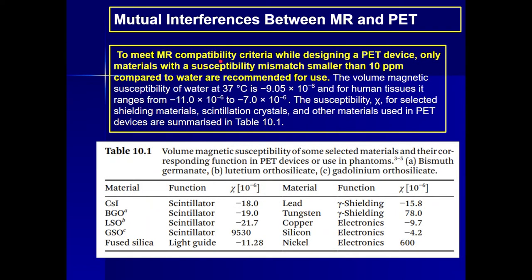To meet MR compatibility criteria while designing a PET device, only materials with a susceptibility mismatch smaller than 10 ppm compared to water are recommended for use. The volume magnetic susceptibility of water at 37 degrees Celsius is minus 9.05 × 10^-6, and for human tissue it ranges from minus 11.0 × 10^-6 to minus 7.0 × 10^-6.